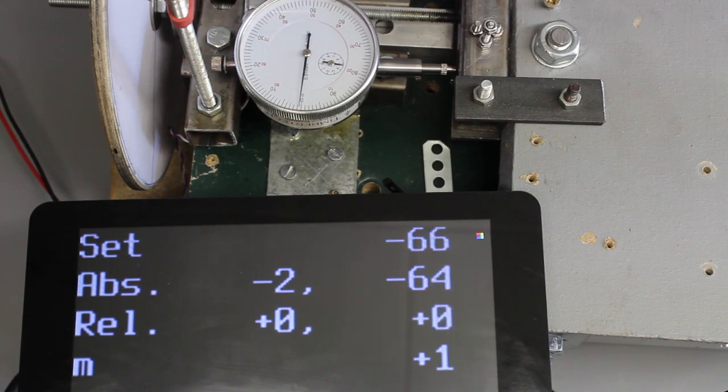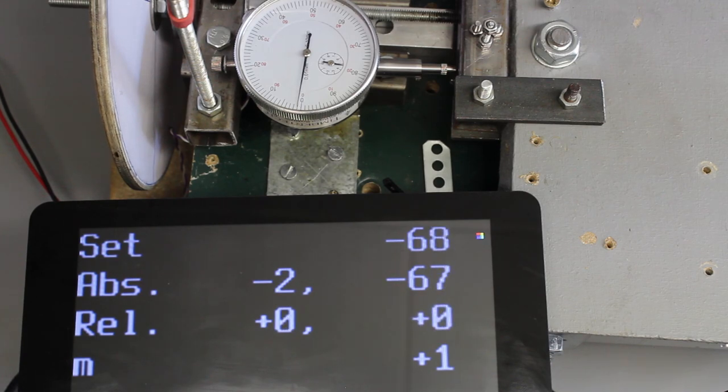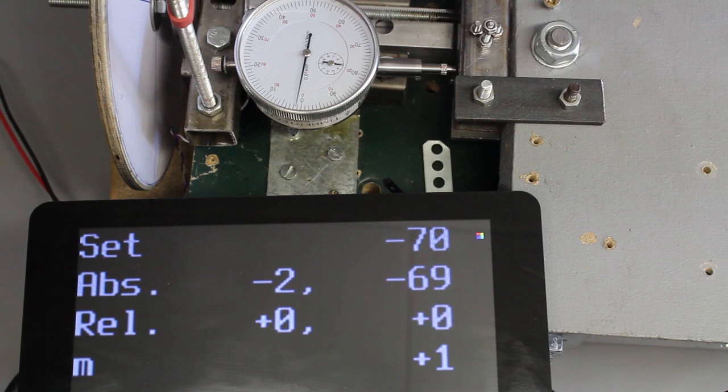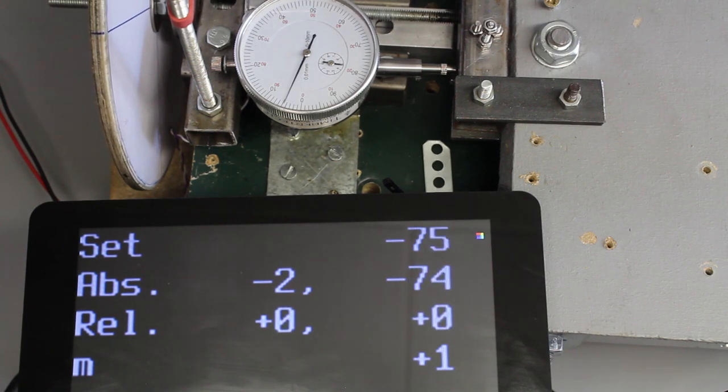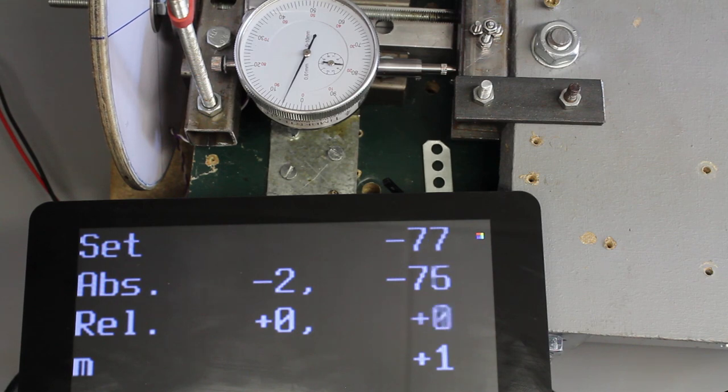In theory, one mouse step equals a movement of 2 micrometers, but as you can see, the indicator turns not in equal steps. The reading is in the range from zero to almost 30 micrometers.